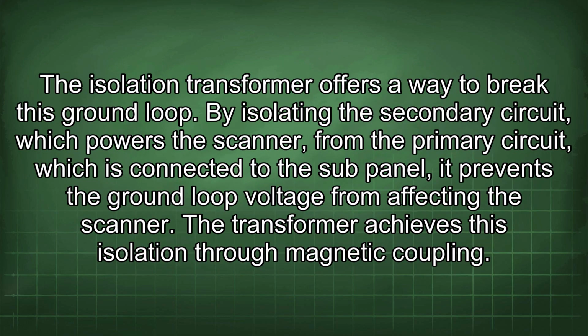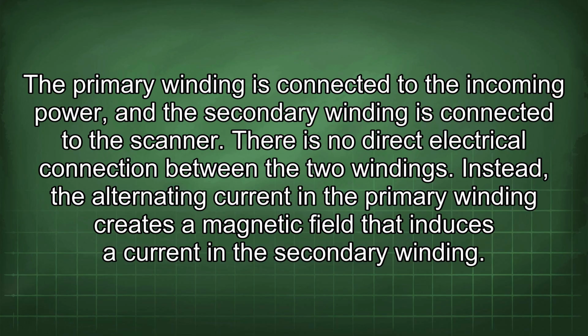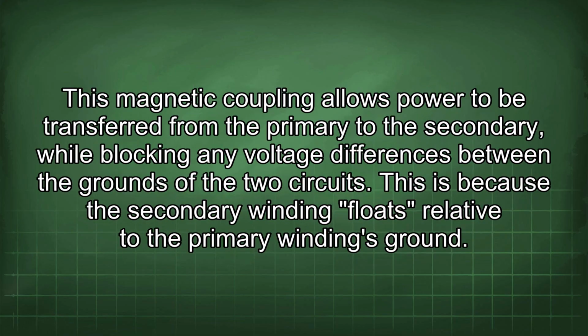The isolation transformer offers a way to break this ground loop. By isolating the secondary circuit, which powers the scanner, from the primary circuit, which is connected to the sub-panel, it prevents the ground loop voltage from affecting the scanner. The transformer achieves this isolation through magnetic coupling. The primary winding is connected to the incoming power, and the secondary winding is connected to the scanner. There is no direct electrical connection between the two windings. Instead, the alternating current in the primary winding creates a magnetic field that induces a current in the secondary winding. This magnetic coupling allows power to be transferred from the primary to the secondary while blocking any voltage differences between the grounds of the two circuits.